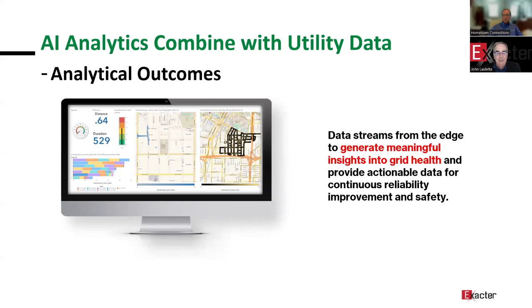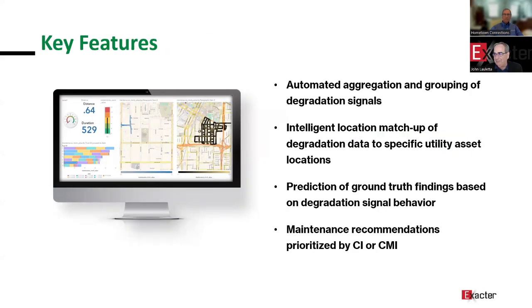The data comes to our customers in almost real time. You see exactly where the surveys ran, the black lines you can see on that chart. You get information about how many CMI, or customer minutes of interruption, will occur if this failure occurs. So you can make judgment calls and prioritize your work in a way that's most effective for you. We aggregate all the degraded signals, and we give you an exact prediction of what's going to fail and how it will affect your operating system.